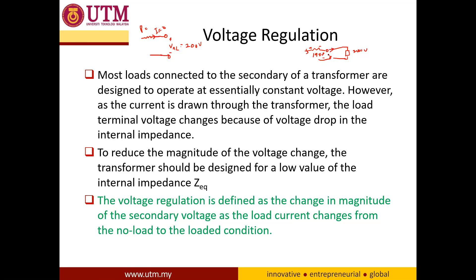So when you connect it with the rated load, this voltage is what we call the voltage full load. As you can see, there is a difference between voltage full load and no-load in terms of value — around 3 volts difference. The good transformer is one that actually has no difference even when it is not connected with the load versus when it is connected with its full load. We know that this internal resistance cannot be avoided, so it's good to have a transformer with a lower voltage regulation percentage.